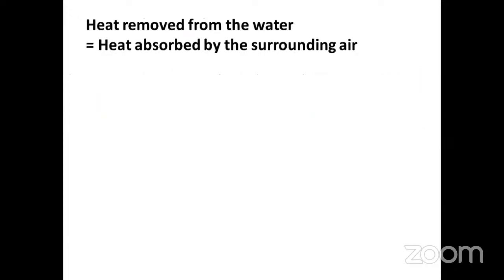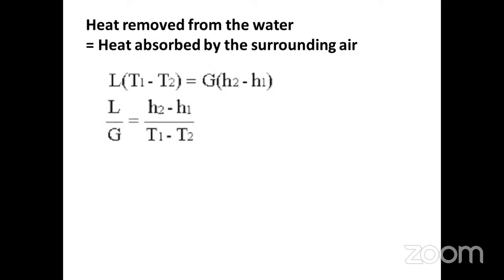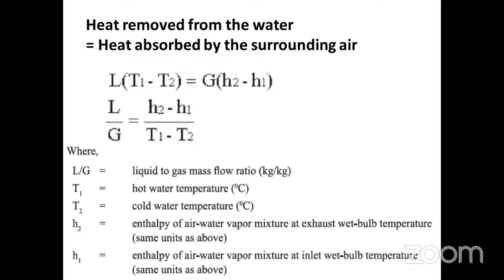L bar G they find out by the formula: heat removed from the water is equal to heat absorbed by the surrounding air. It is purely thermodynamics. And this is the formula. L bar G is equal to enthalpy difference divided by temperature difference. Simple formula only. L means the liquid flow, G is the gas mass flow. We cannot measure it directly. So L bar G ratio is the enthalpy of air-water mixture at the exhaust wet bulb temperature; H1 is at the inlet wet bulb temperature; T1, T2 are hot water and cold water. That's all. It's a formula.